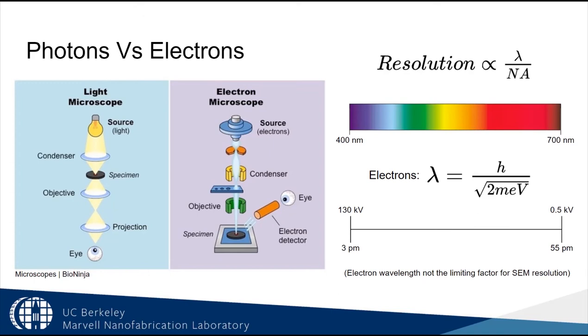In contrast, the wavelength of an electron is a function of its energy. In an SEM, that means the wavelength depends on the accelerating voltage. In the nanolab, we can accelerate electrons between half a kilovolt and 130 kilovolts. That means that the electron wavelengths range from 3 picometers to 55 picometers. In theory, that means we could image individual atoms. Sadly, that's not the limiting factor for SEM resolution.